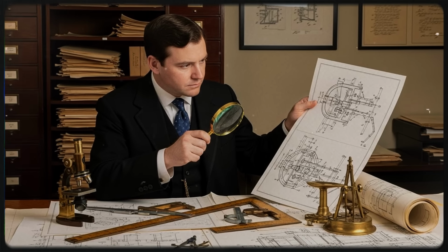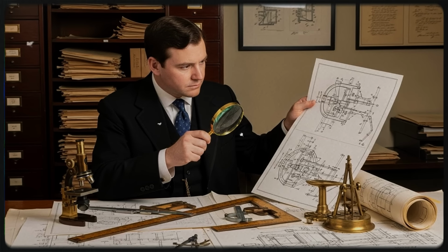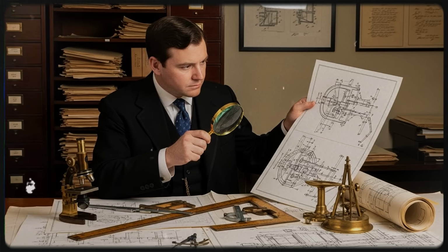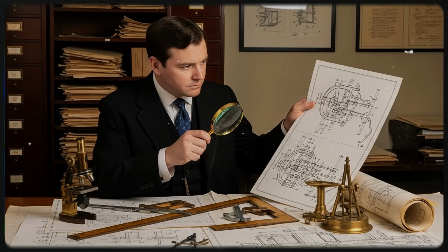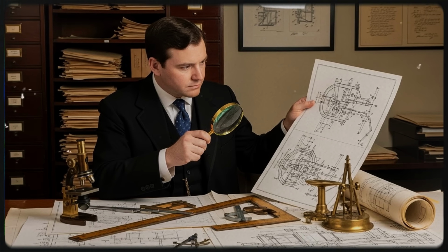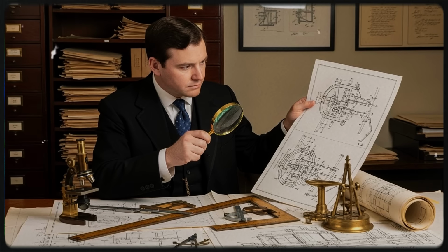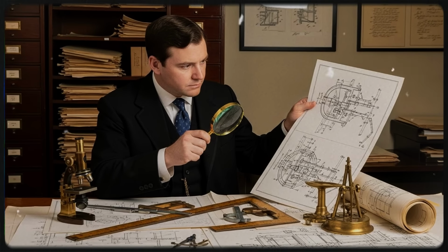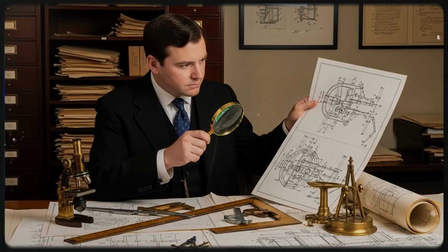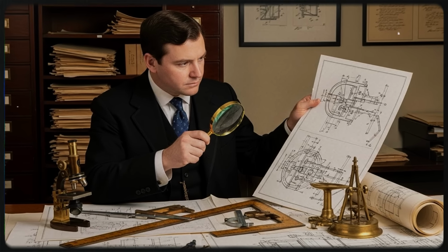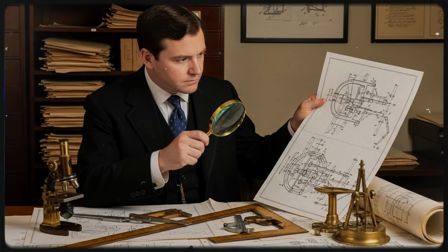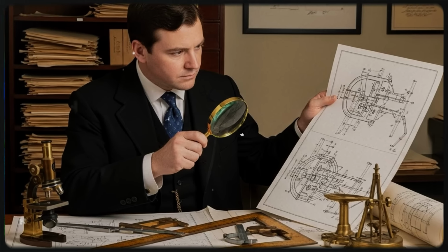More sophisticated circuit breakers used trip coils for both overcurrent and thermal overload. A bimetallic element heated up with direct current. Prolonged moderate overload caused gradual heating of the bimetal until it bent sufficiently to trigger mechanical opening. A sudden short circuit caused instantaneous tripping through magnetic attraction. Two independent protection mechanisms in the same device.